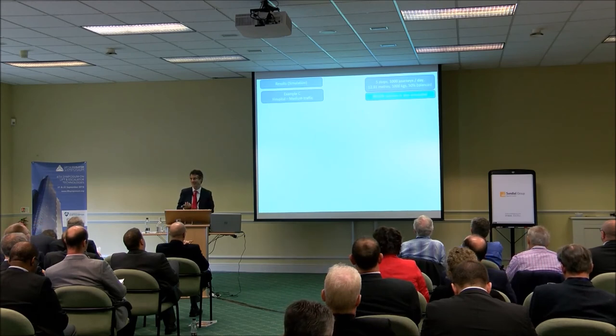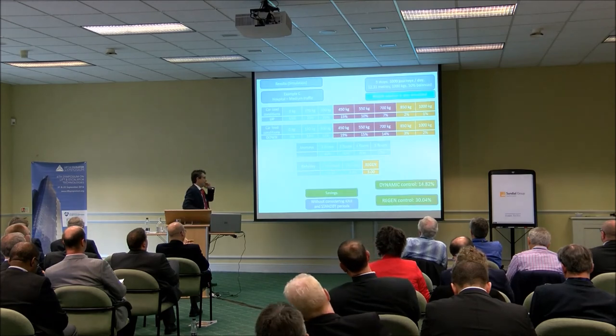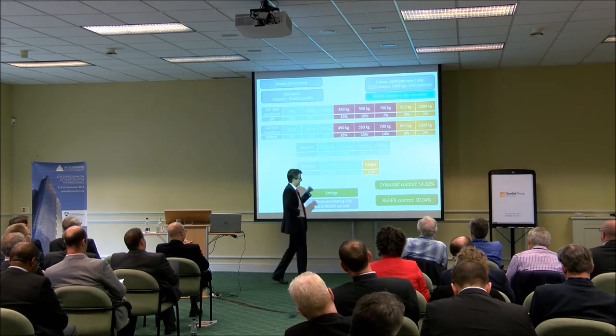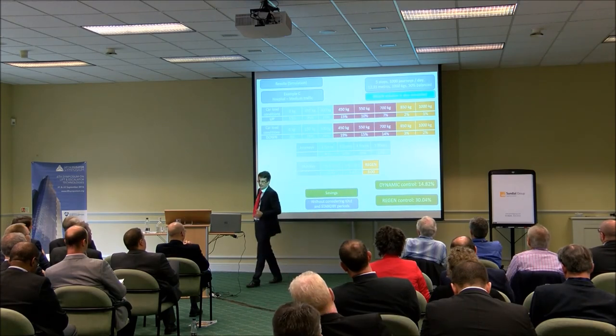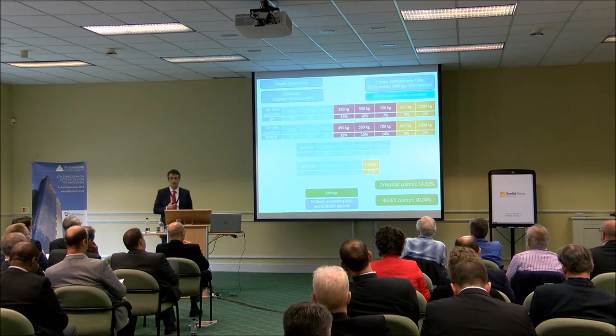The last example is a hospital with a medium traffic lift of 1,000 journeys per day, where we also apply a regen system. We found that dynamic control can achieve approximately 15% savings and regen control can achieve 30% savings. However, we did not take into account the idle and standby periods.